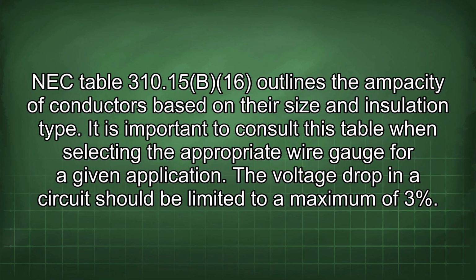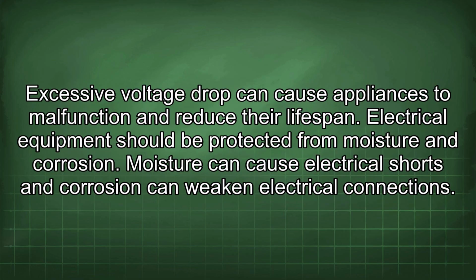NEC Table 310.15(B)(16) outlines the ampacity of conductors based on their size and insulation type. It is important to consult this table when selecting the appropriate wire gauge for a given application. The voltage drop in a circuit should be limited to a maximum of 3%. Excessive voltage drop can cause appliances to malfunction and reduce their lifespan.